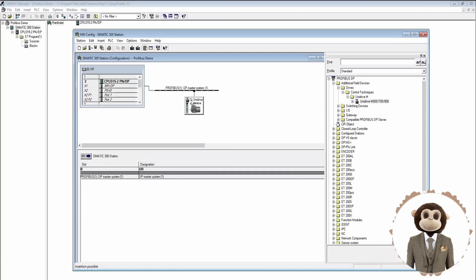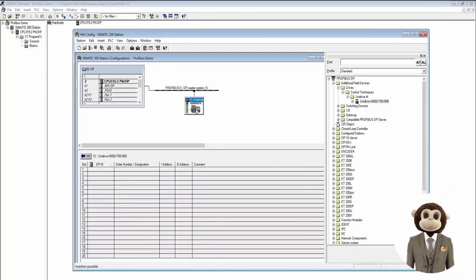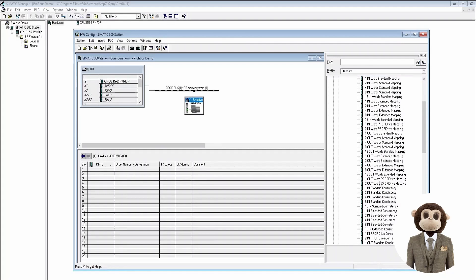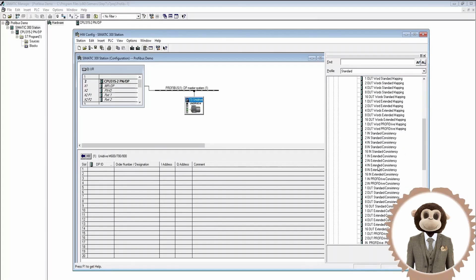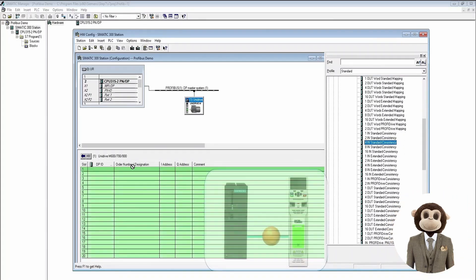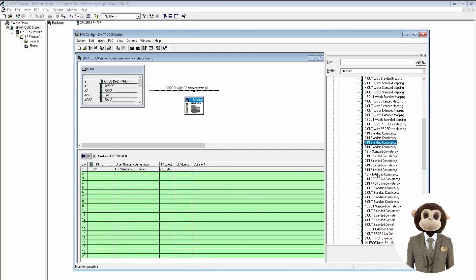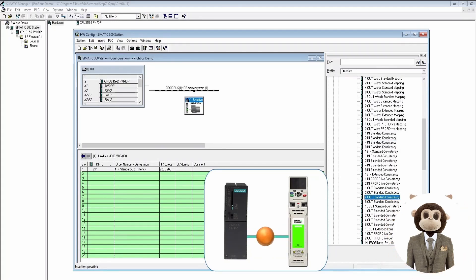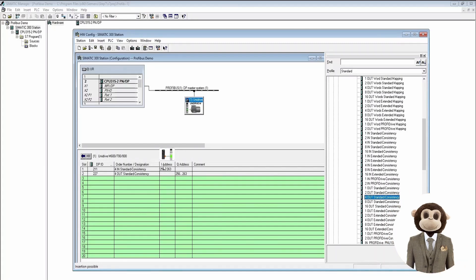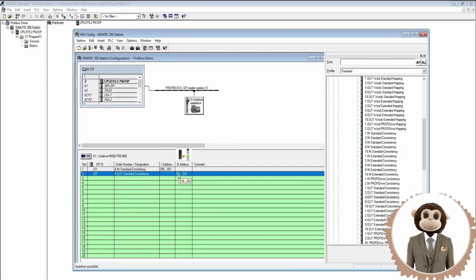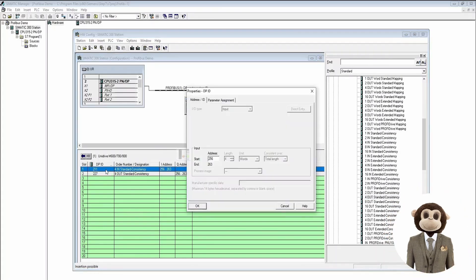We can see the node address in parentheses for the drive. Now we want to add the configuration for reading and writing. In this setup we're going to use four input words with standard consistency and four output words with standard consistency, and drag those over. Notice the input address starts at 256 through 263, and the output address is also 256 through 263. We could change those addresses, but the defaults work.